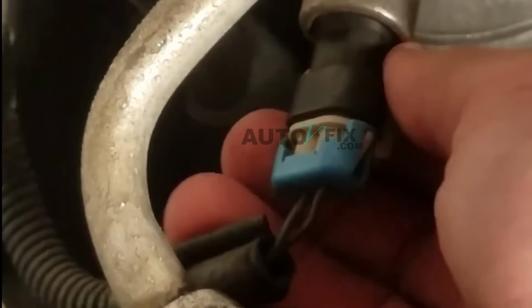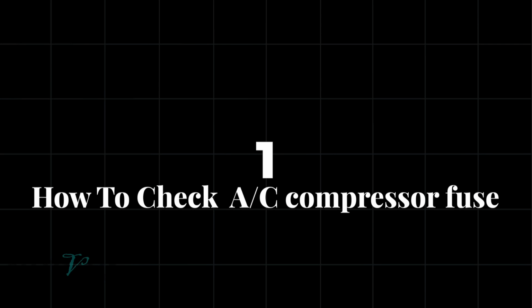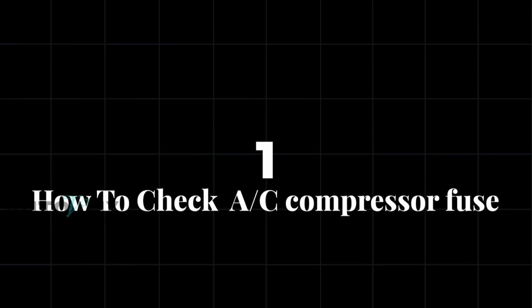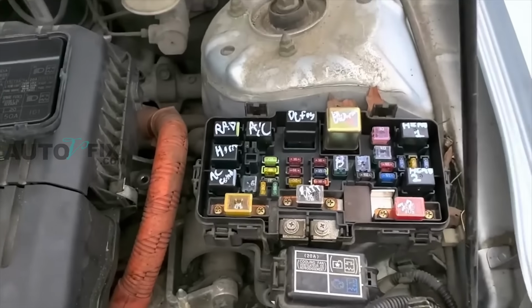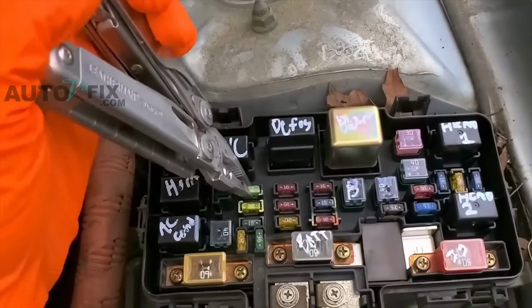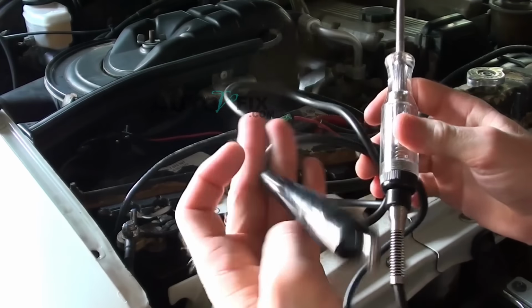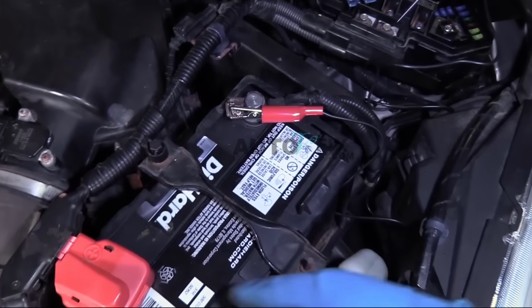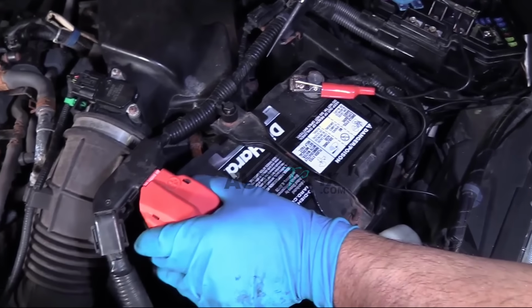Now before we test the pressure switch, check the cheap electrical parts first. Start with the AC compressor fuse. Do not just look at the fuse and assume it is good. Pull the fuse out and inspect it, or better, use a test light. Clip the test light to a good ground. You can use the battery negative terminal or a clean metal ground point.